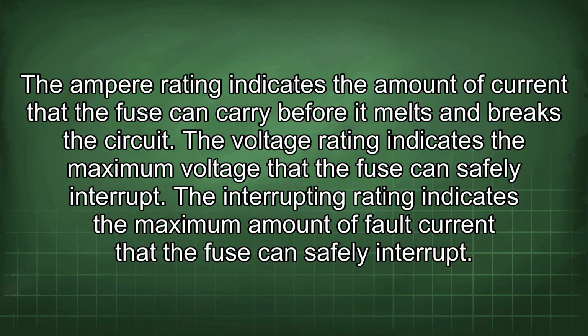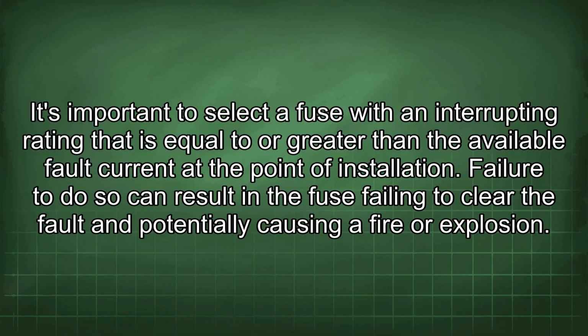The ampere rating indicates the amount of current that the fuse can carry before it melts and breaks the circuit. The voltage rating indicates the maximum voltage that the fuse can safely interrupt. The interrupting rating indicates the maximum amount of fault current that the fuse can safely interrupt. It's important to select a fuse with an interrupting rating that is equal to or greater than the available fault current at the point of installation. Failure to do so can result in the fuse failing to clear the fault and potentially causing a fire or explosion.